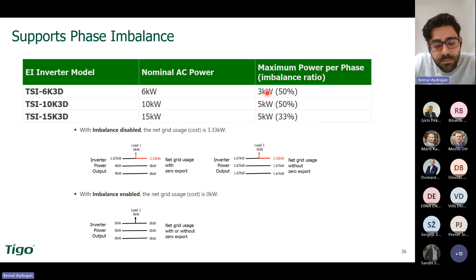So to sum up, the inverter has a zero export feature, which means that if you need, you can enable it, and you're not going to export any power to the grid. If imbalance is disabled, meaning it is a regular inverter, then to support 5 kilowatts of imbalanced power use you need to use 3.3 kilowatts from the grid, with or without zero export. And if you enable the imbalance power mode, you are not going to use the grid, because the inverter supports 5 kilowatts of phase imbalance. This is the maximum imbalance ratio per inverter. For 6 kilowatts, it is 3 kilowatts of phase imbalance. For the others, it's 5 kilowatts. So the last component of the system is the EI battery storage component.